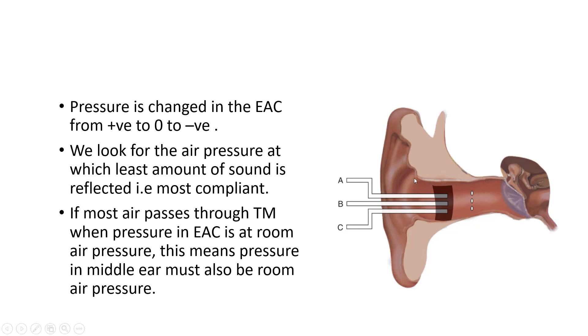In tympanometry, a probe is inserted into the external auditory canal that smoothly fits, and then we create an airtight seal. The probe that we use consists of three chambers: chamber A, B, and C. Chamber A is an oscillator that produces a sound of 226 Hz frequency. Some resistance is provided by the tympanic membrane — some sound is absorbed and transmitted while some is reflected back. The reflected sound waves are recorded by chamber C, which is a microphone. This records how much of the sound waves are reflected.